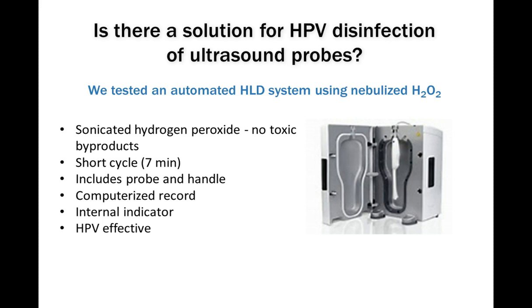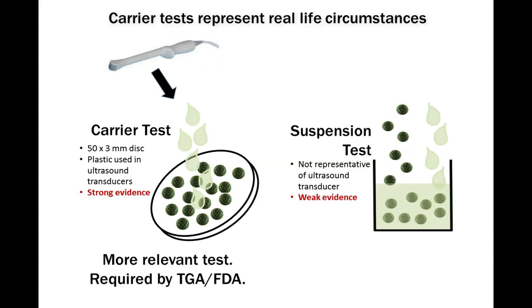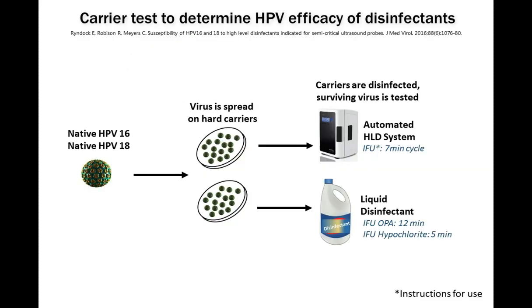It includes a probe and the handle. They both fit inside the machine. It provides a computerized record. It has an internal indicator, and we have shown now that it's HPV effective. So in the first test, we did suspension tests, but actually the carrier or the solid material test represents more real-life circumstances. So we use these carrier discs, which are made from the same plastic used in ultrasound transducers. And this is a more relevant test and required by the TGA and the FDA, as opposed to our previous suspension test.